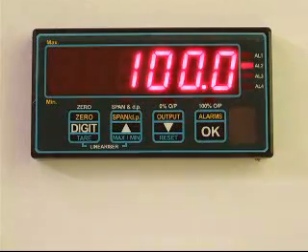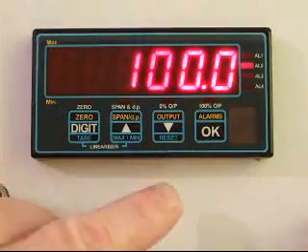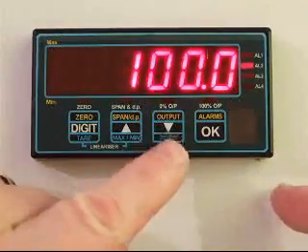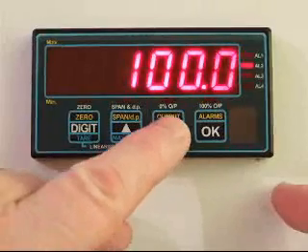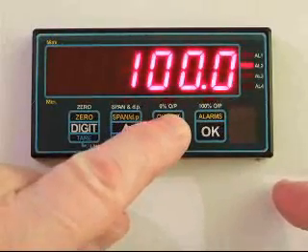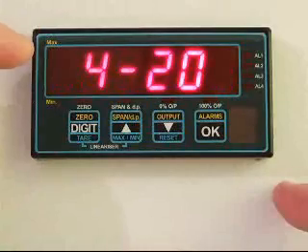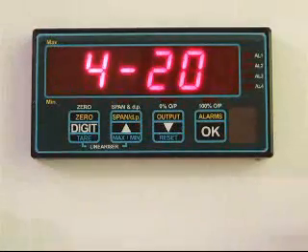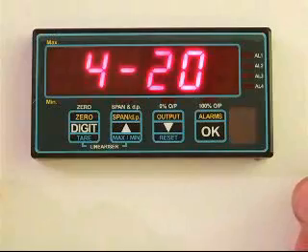Move that to the off position, and now you'll be able to set your analog output by pressing the output button for about three seconds. So if we press that for three seconds, the meter will confirm that we're in the output. And at the moment I've got four to twenty milliamps selected as my output range.